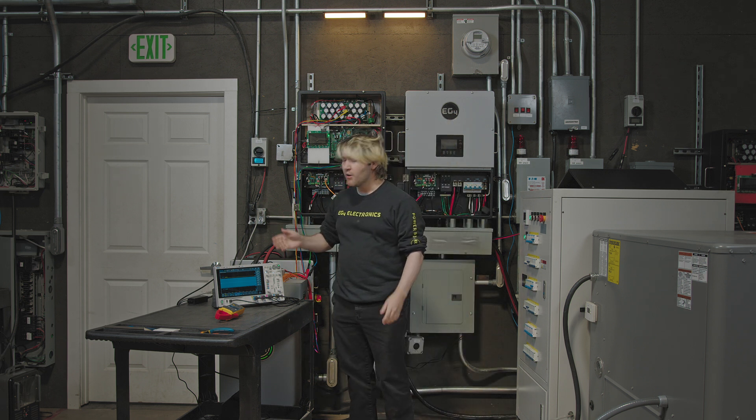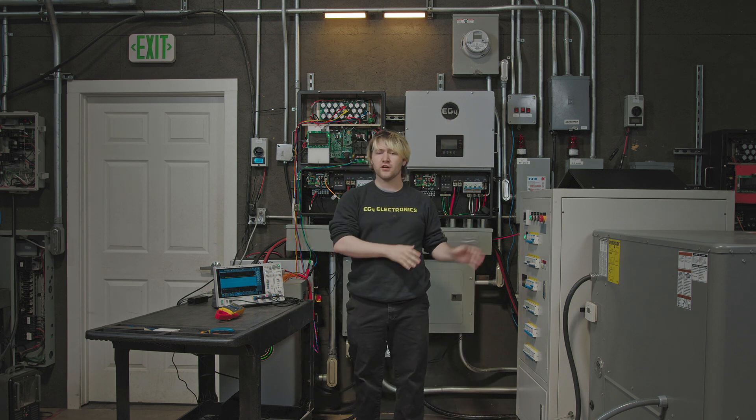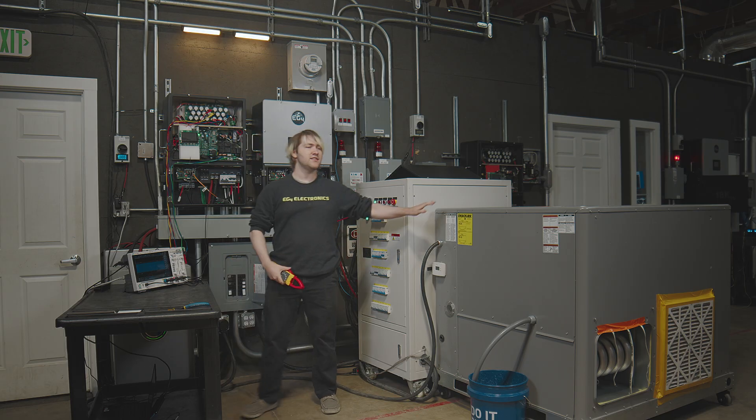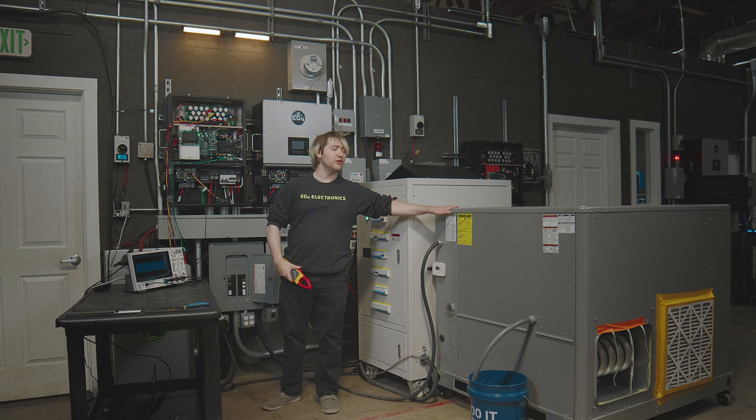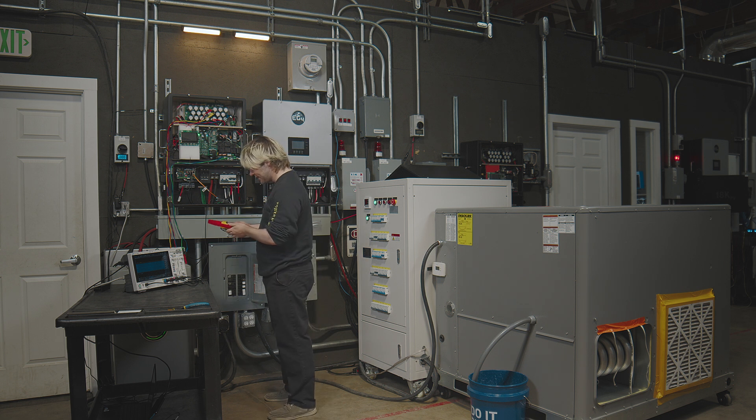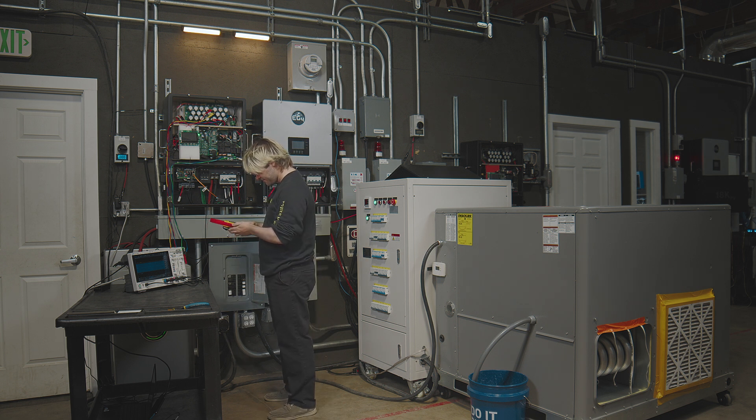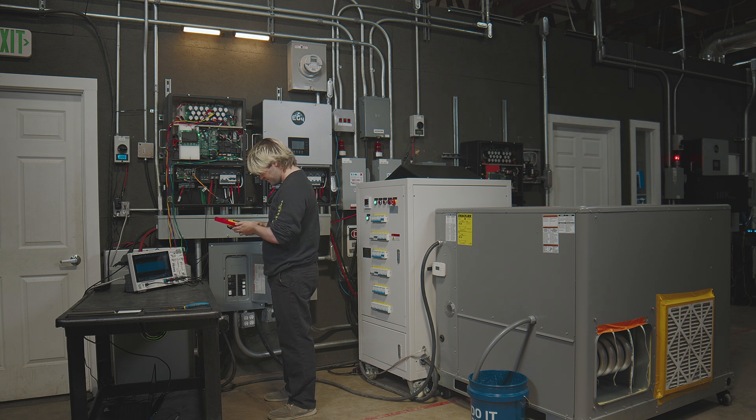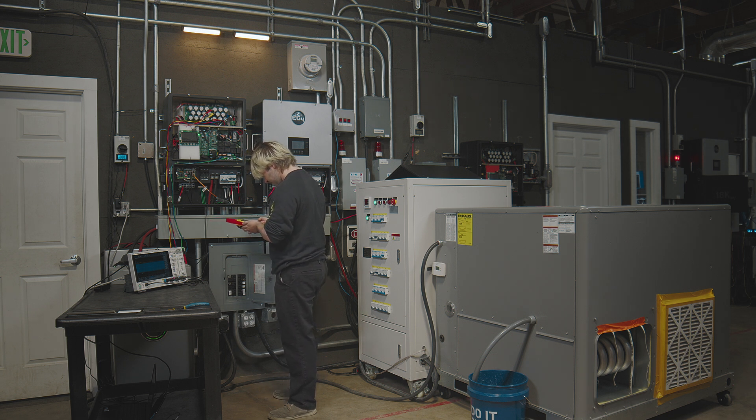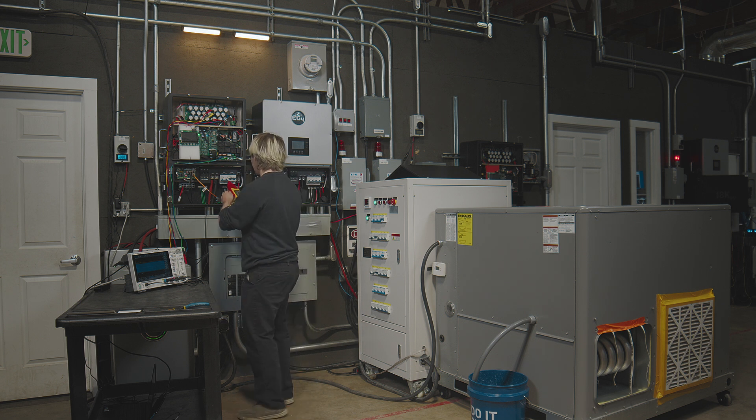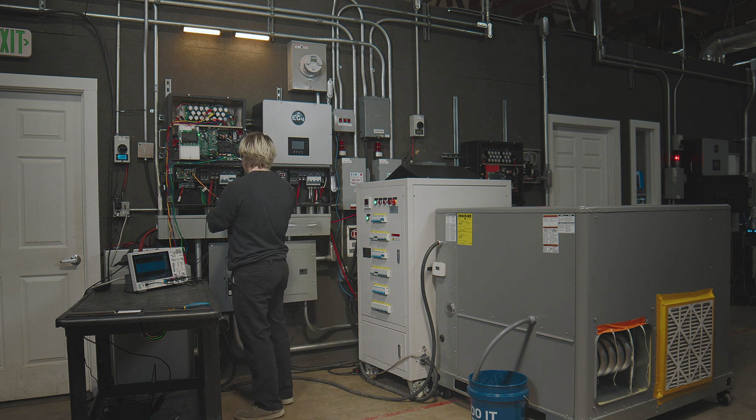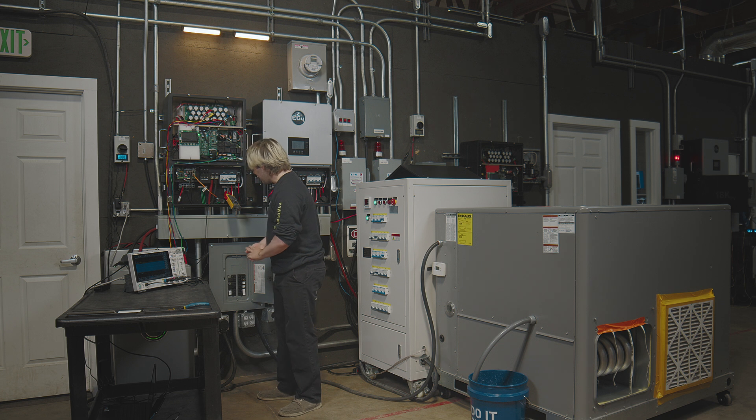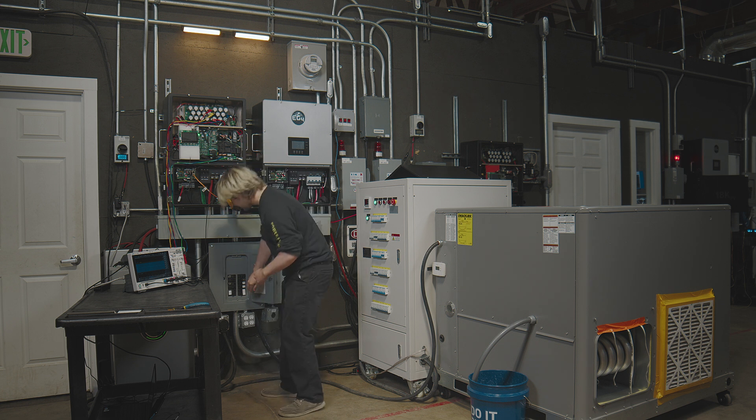Before we start the configurable load bank, I'm going to test the inrush current of the five-ton AC. So let's go ahead and set up an amp meter here. Get that on there and we're going to start the five-ton.